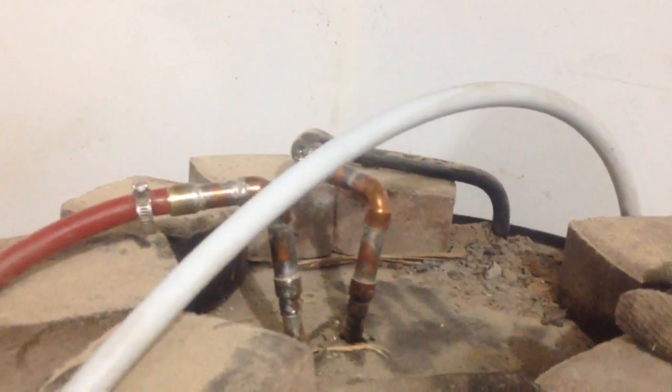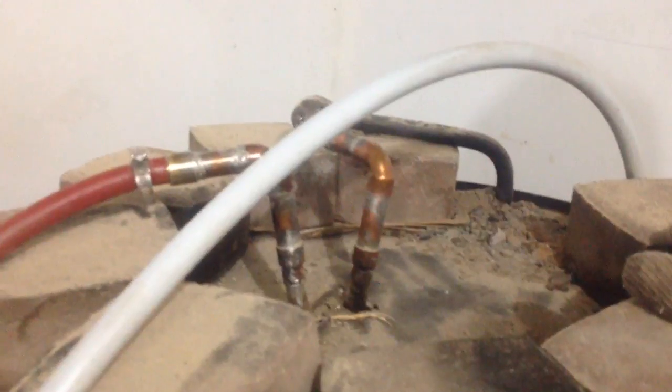As I mentioned before, I got about 200 feet of PEX. It's actually just laying outside right now. Sorry, my shop's a mess — it's laying outside in black foam insulation, and in my shop I don't have it insulated yet. I'm only losing about 3 degrees from here to the house.